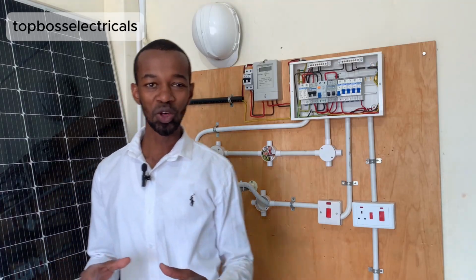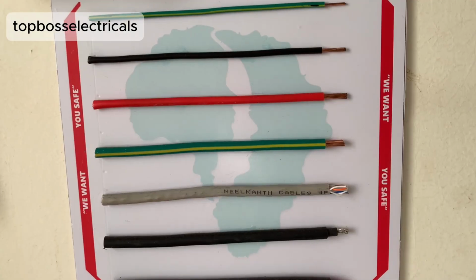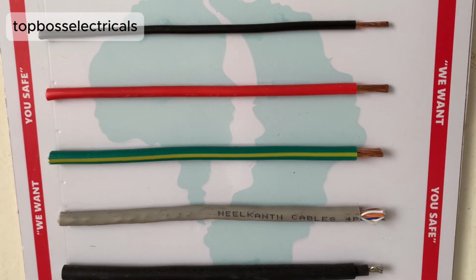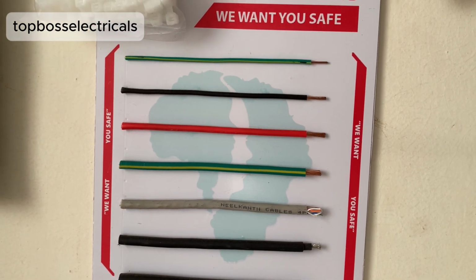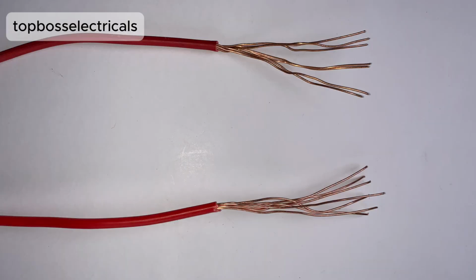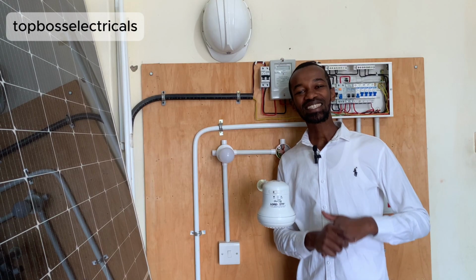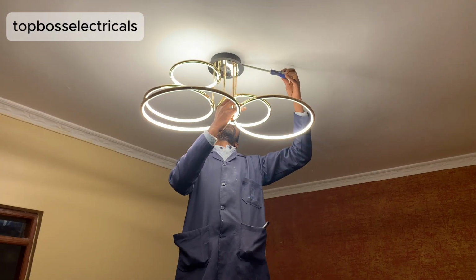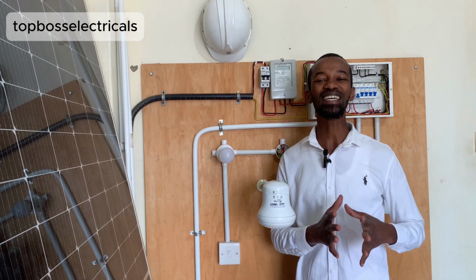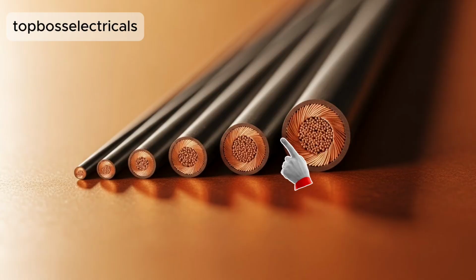My top boss, did you know that different cable sizes have different resistance on them? And that is the reason why for you to select a certain cable for a certain circuit, the size of the cable must be considered. When we talk about size here, what are we talking about? We are referring to the cross-sectional area.